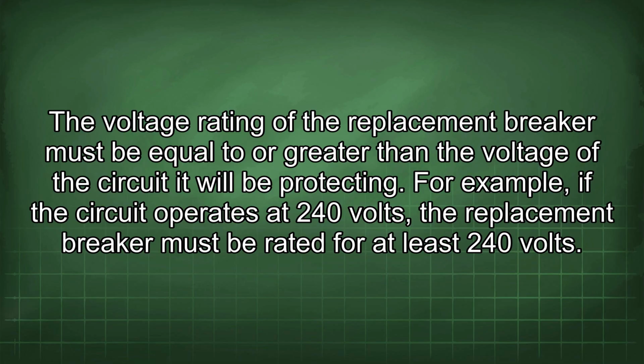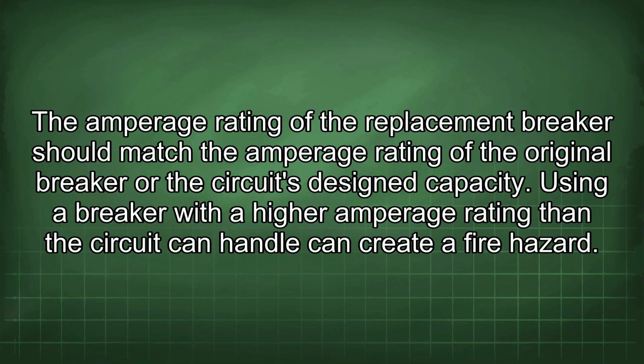The voltage rating of the replacement breaker must be equal to or greater than the voltage of the circuit it will be protecting. For example, if the circuit operates at 240 volts, the replacement breaker must be rated for at least 240 volts. The amperage rating of the replacement breaker should match the amperage rating of the original breaker or the circuit's design capacity.